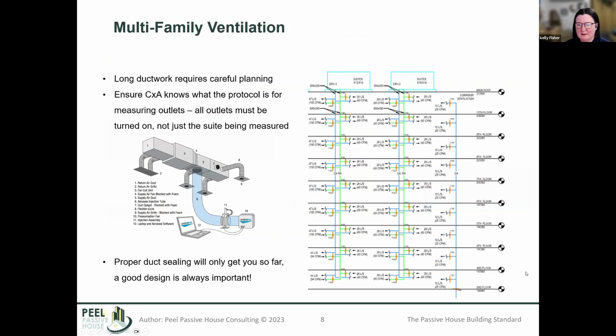But with multifamily ventilation, we end up with a lot of really long ductwork. Here's an example of, I believe, a 10-story project. There were roof-mounted ERVs that distribute vertically down into all the suites, so it goes from the roof of a 10-floor building to the ceiling of the second floor. This particular project got AeroSeal on the ductwork, so it made it really easy to understand if there was going to be any leakage. But we still needed to be mindful of proper design and testing those pressure losses with the mechanical engineer through design, to make sure that while we are designing a system that is going to be tight and mitigate that leakage, we still need to make sure that it can perform properly. So make sure you're doing the calculations and fully assessing all of the little components that run in your ducts. And I've got some examples of what those look like here.